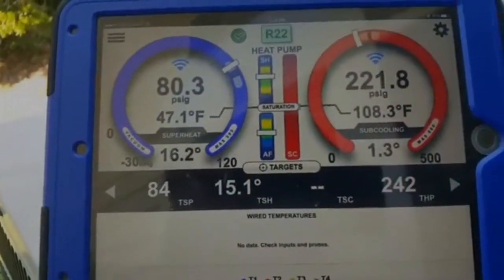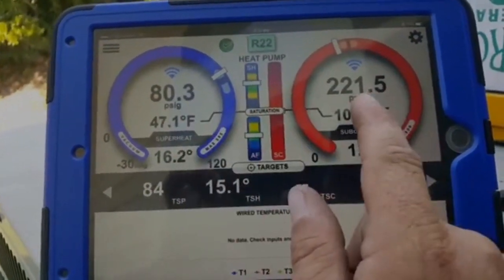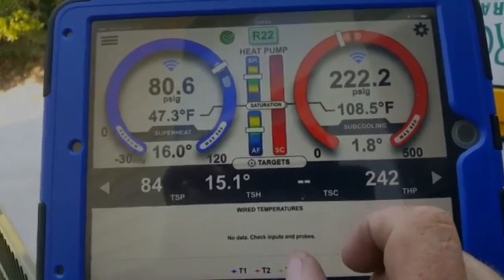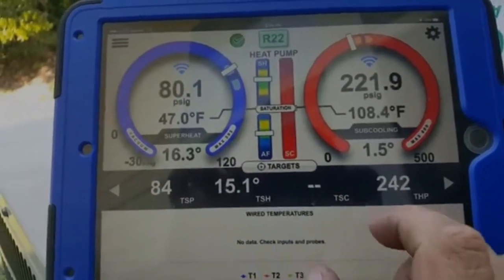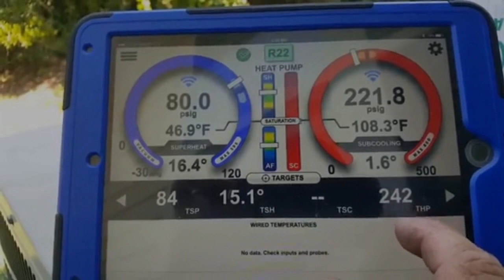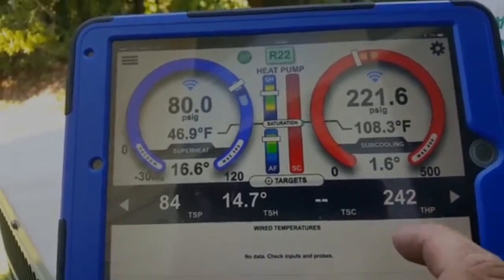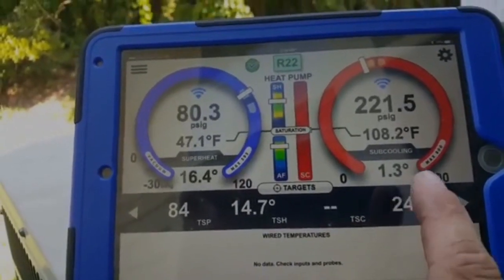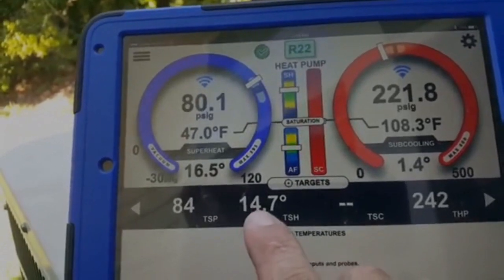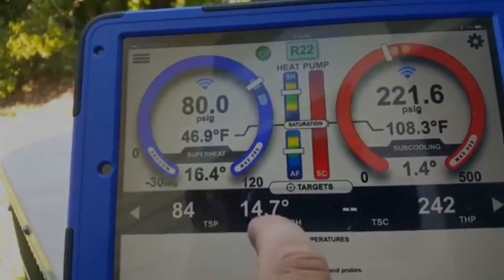Guys, I got it about where I'm going to leave it. 80, 221, only 1.5 degrees of subcooling, 2 degrees of subcooling. See our target head pressure is a little bit higher than that. One of the reasons is it does 10 SEER on that estimation. We have 14.7 target superheat. Our superheat's almost dead on.